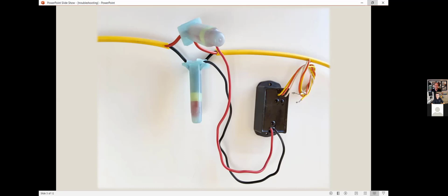The other one that happens is when we have corrosion on the two-wire path and those splices aren't real solid, they don't have a good metal-to-metal contact, we might get the infamous error 7. And it's essentially a communication error. That means the device isn't able to communicate back with the controller. Our devices are not just decoders, we call them bicoders because they're bidirectional. We'll send out a command and they get a reply back. If it doesn't get that reply back, or there's another communication issue, those are even harder to troubleshoot, but they almost always come back to wire integrity and wire issues.